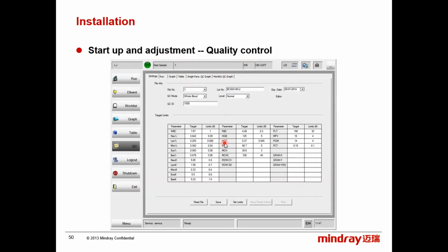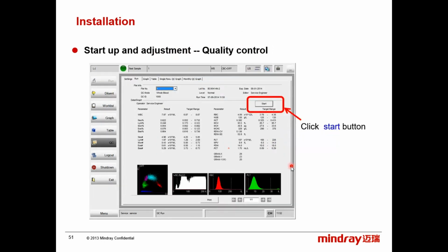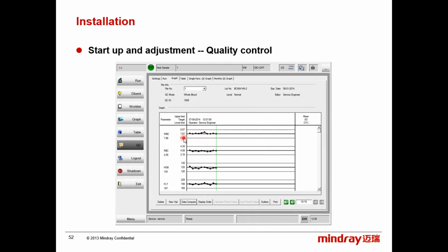This is quality control settings. You can read the file directly or set them manually. You press start. Of course, guys, it is important to keep in mind that you do not run the QC as a normal sample, because the analysis algorithm is not the same. The QC is not entirely human blood. It has bovine origin, so be careful about this. If you run it as a sample, you will not get good results, good scattergrams and so on. So just run it from the QC part. This is just the Levey-Jennings.